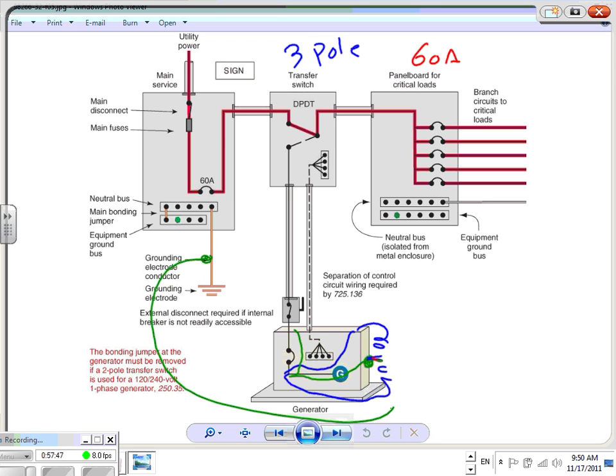If I want to make it a non-separately derived system, by code I have to drive a ground rod if it's outdoor. Now my ground rod goes and bonds the frame. Look what I did: I took the ground rod and tied it to the frame. I still have to do that. If the generator is outdoor, tie the frame of the generator to the ground rod. I still have to tie the 2 ground rods together, here and here, if they're not the same ground rod.